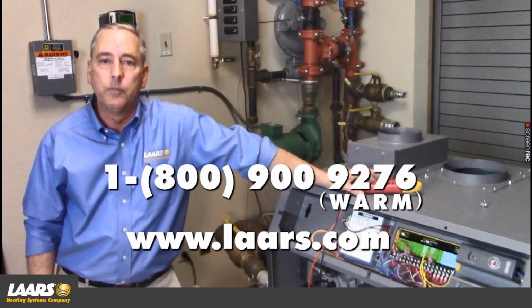You have 4 seconds to prove flame, rectify, and then that igniter drops out. So that's why you saw at one point, it was either 3.4 or 3.7. I think it was 3.4 amps on the first test we showed. And then it dropped out after that. So that was your ignition. Once we've proven flame, shuts the igniter off. We're still in flame sense, and we just keep the burners running or gas valves energized.